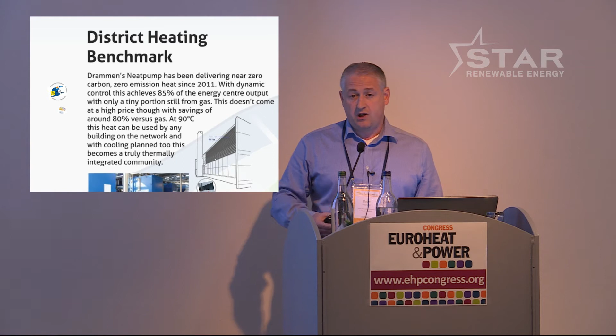So it was built, they're very proud of it, it's in a glass-fronted building, and they're now getting round about 14 megawatts of heat at 90 degrees from seawater. So the seawater is only about 4 degrees after we finish cooling it. We cool it from 8 down to 4, and that's pretty much all year round they can achieve that. Obviously the heat demand varies. They go from about 2 megawatts in summer, up to around about 14 megawatts in spring and autumn, and in the heavy winter months they bring gas in on top of that.